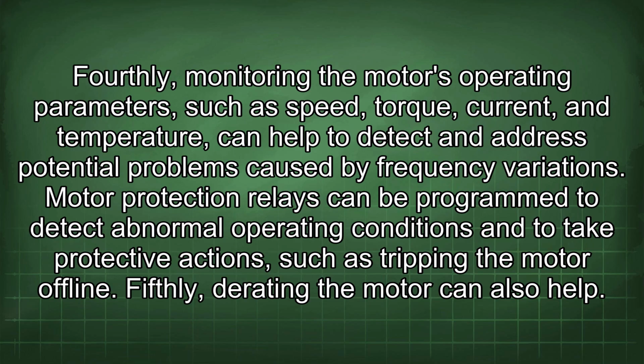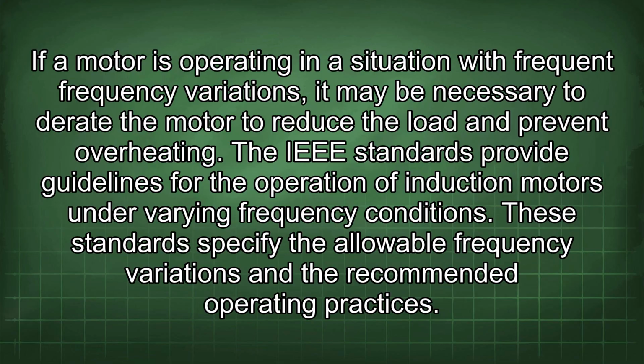Motor protection relays can be programmed to detect abnormal operating conditions and to take protective actions such as tripping the motor offline. Fifthly, derating the motor can also help. If a motor is operating in a situation with frequent frequency variations, it may be necessary to derate the motor to reduce the load and prevent overheating.